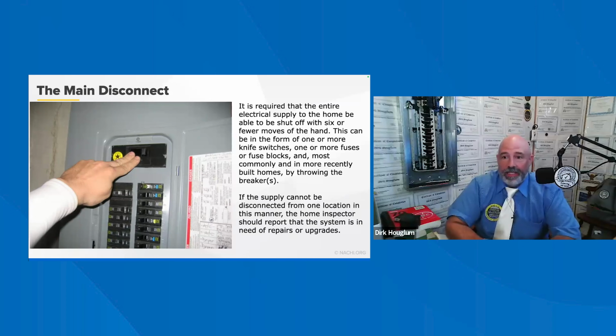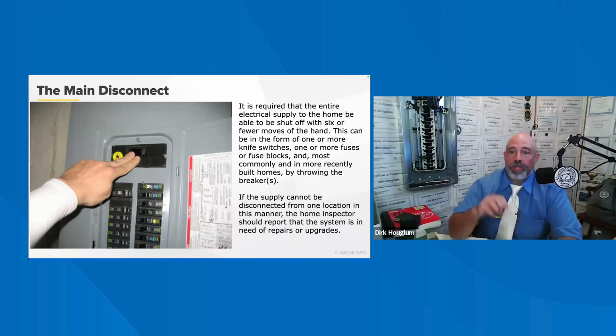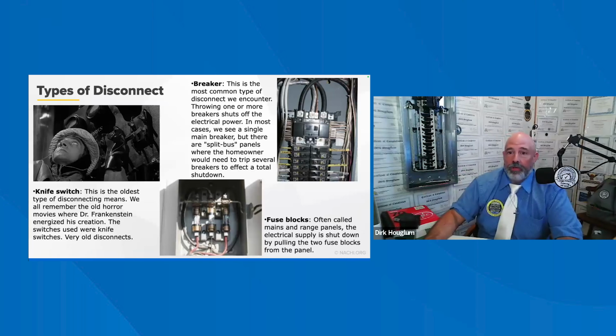The service equipment is necessary equipment. It usually consists of a circuit breaker, switches, and fuses and accessories connected to the load end of the service conductors to the house, and is intended to constitute the main disconnect means for the service. This disconnect means should be located outside or inside as close as possible to the point of entrance of the service conductors that are coming in. The service equipment should be identified with markings as a service disconnect. A common service size for a single family house these days is 200 amps, but it has to be at least 100 amps. Okay. There are different types of disconnects depending on the age of the property.